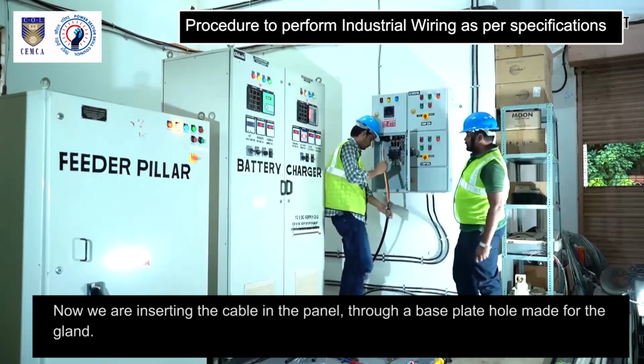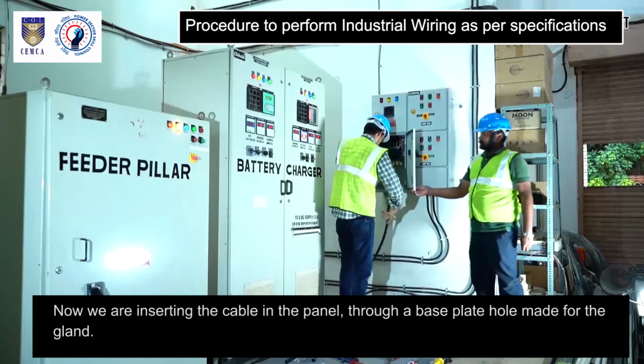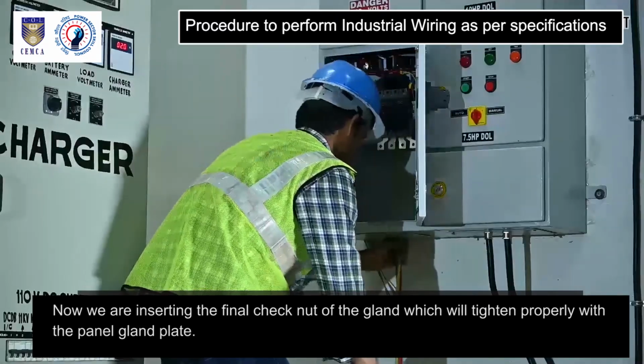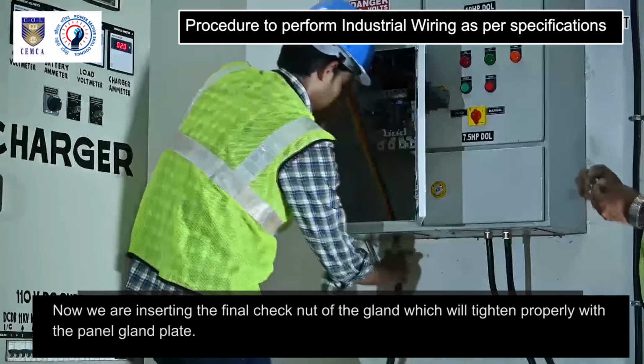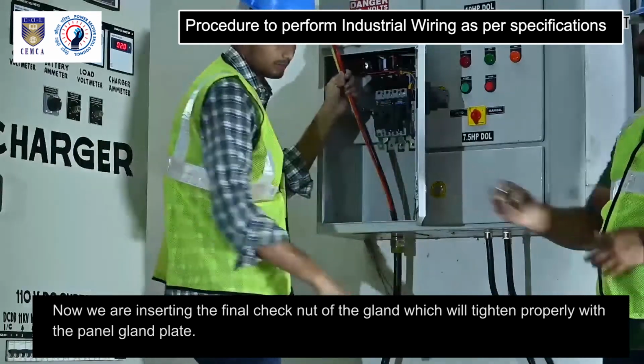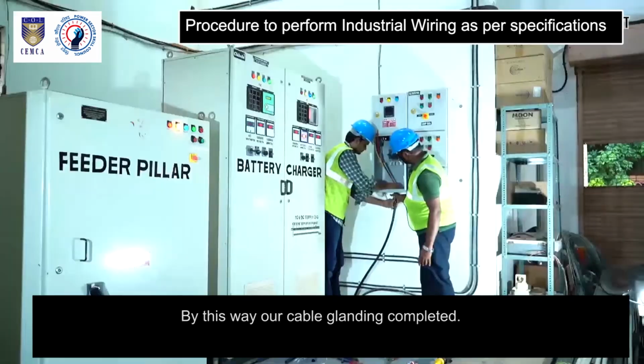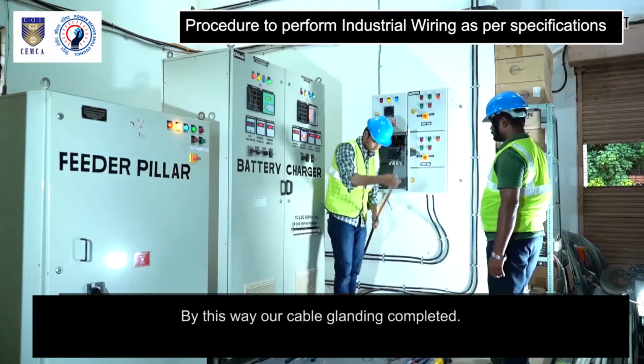Now we are inserting the cable in the panel through a base plate hole made for the gland. Now we are inserting the final check nut of the gland which will tighten properly with the panel gland plate. By this way our cable glanding is completed.